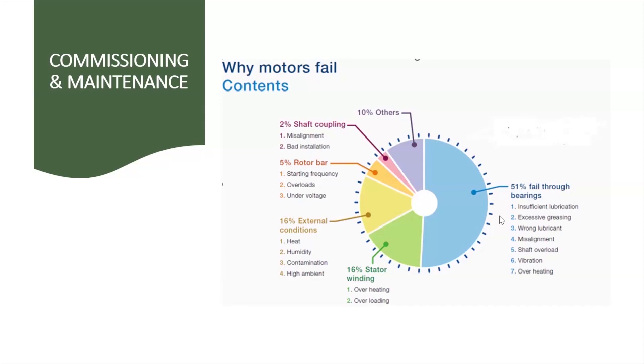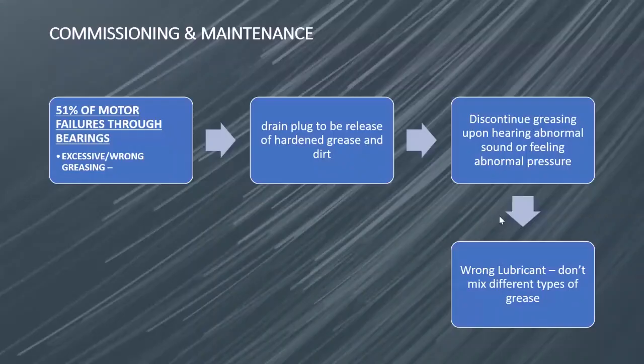But most of the time, bearings are normally not taken very good care of by electrical maintenance professionals. Their attention is most of the time on the windings, but windings account for only 16% of failures recorded, which means that bearing failure needs to be critically looked at in terms of electrical motor maintenance. So, bearing failure: which issues cause the bearing to fail? Excessive greasing or wrong greasing has been found to contribute to a lot of motor bearing failure.